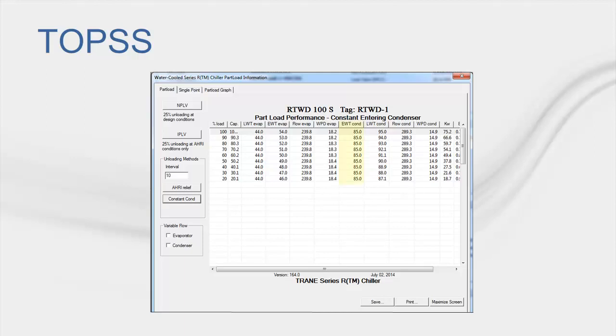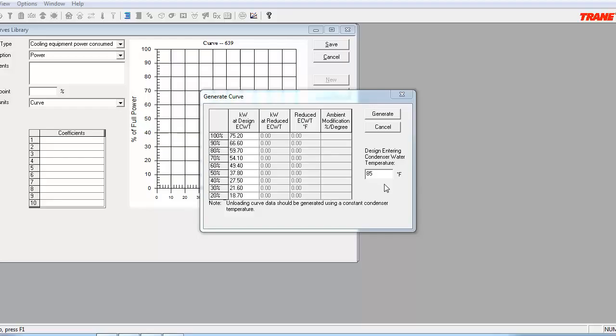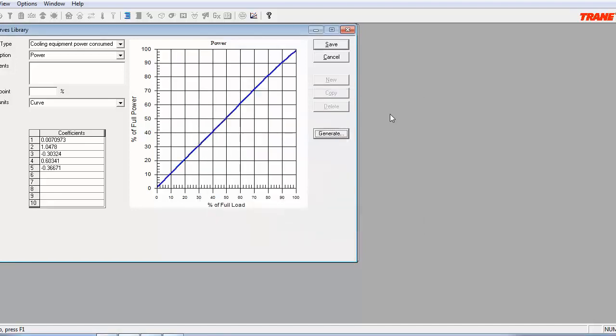Note that the EWT Cond, or Entering Water Temperature for the Condenser column, is consistently 85 degrees Fahrenheit for all load points. Back in the Curves Library, you can see that I have populated the KW column with the data provided by TOPSS. With this completed, I can click on the Generate button and the program will plot out the graph for the Power Consume Curve. Note that since the data we were provided with by TOPS stopped at 20% load, we will enter in 20% as our cycle point. That does it for the Power Consume Curve. Now I can click on Save.